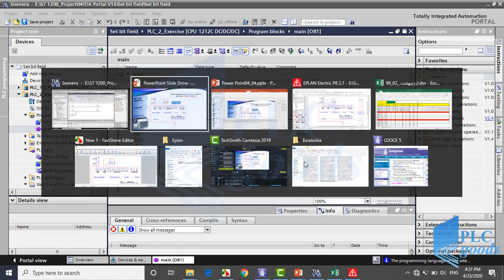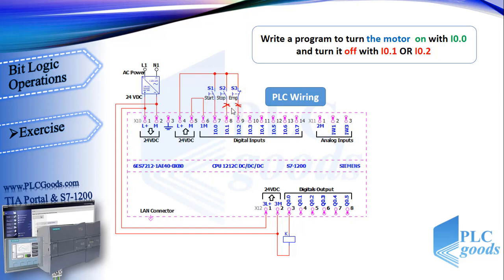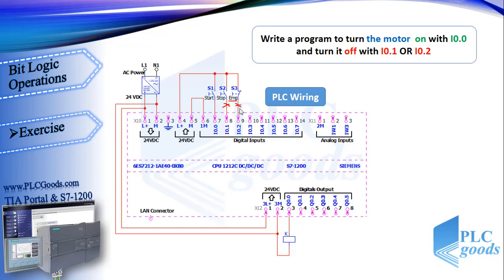Okay, we reached the end of this video but let me say a point about this PLC wiring. Why don't we use a normally open push button for emergency? See here, suppose these two wires have been disconnected and we don't know yet. Then if I press stop push button, the motor won't stop. Thus I start to find this problem, but in an emergency condition we don't have any time. With this wiring, if either emergency push button is pressed or its wiring is disconnected, PLC will turn off the motor. So before I need to use emergency push button, I can find this problem.